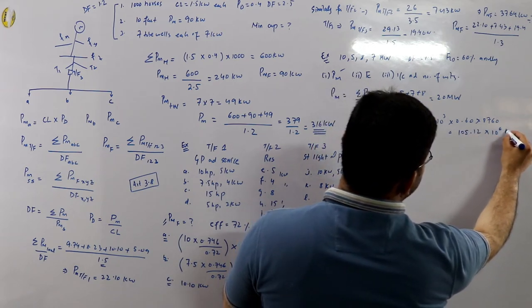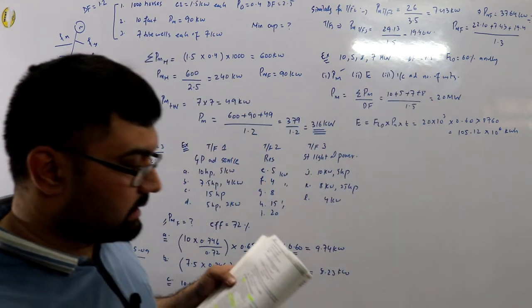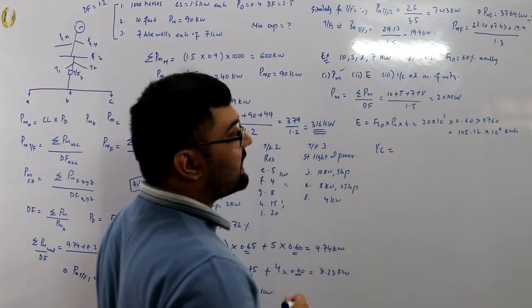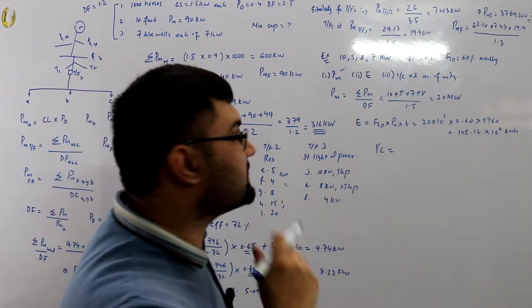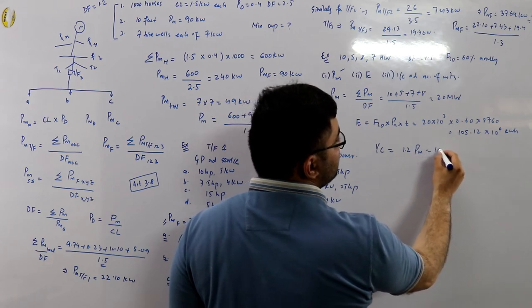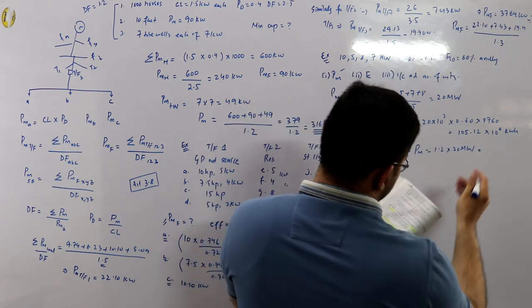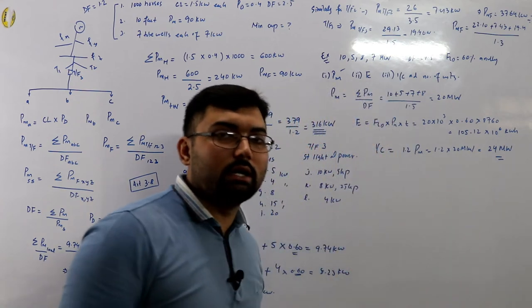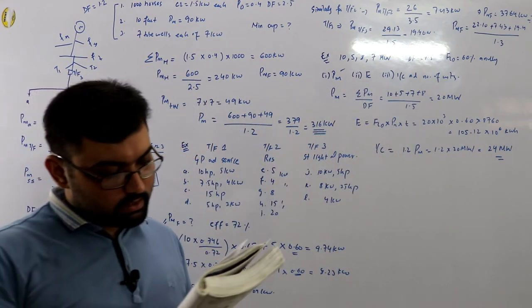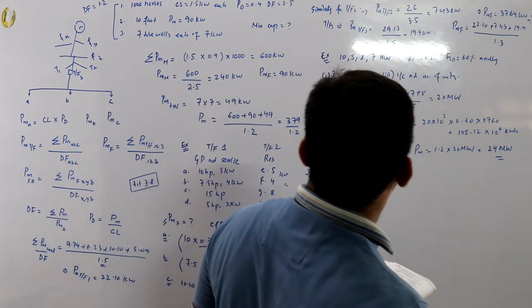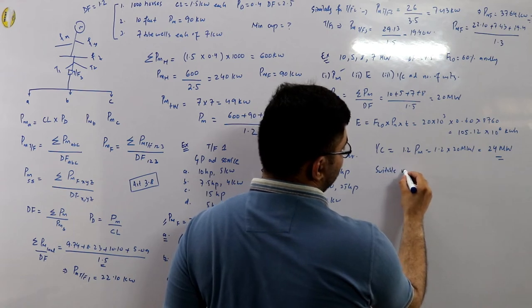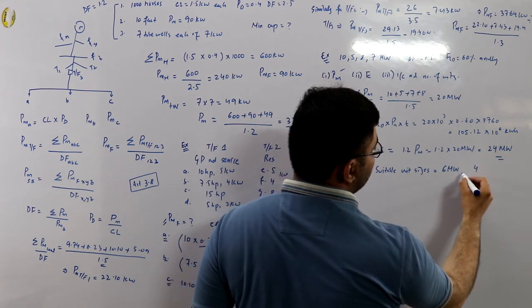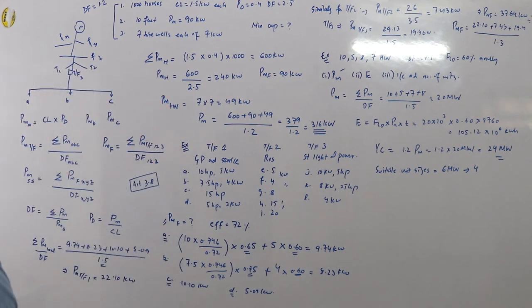The energy comes out to 105.12 × 10⁶ kWh. For installed capacity, it should be at least equal to the maximum demand, but with 20% extra: 1.2 × 20 = 24 megawatts. Suitable unit sizes are four units each of 6 megawatts, which fits the load curve economically.